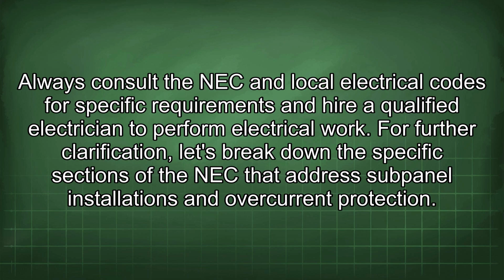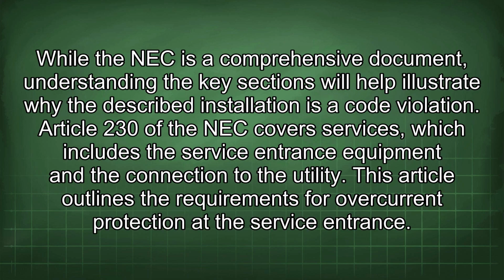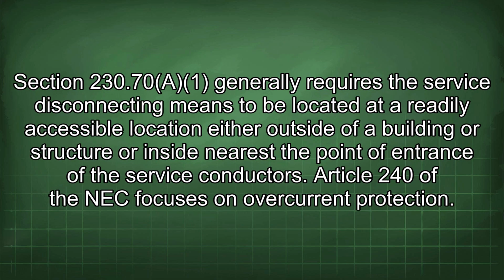For further clarification, let's break down the specific sections of the NEC that address subpanel installations and overcurrent protection. While the NEC is a comprehensive document, understanding the key sections will help illustrate why the described installation is a code violation. Article 230 of the NEC covers services, which includes the service entrance equipment and the connection to the utility. This article outlines the requirements for overcurrent protection at the service entrance. Section 230.70(A) generally requires the service disconnecting means to be located at a readily accessible location either outside of a building or structure or inside nearest the point of entrance of the service conductors.